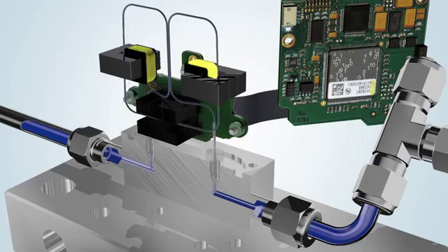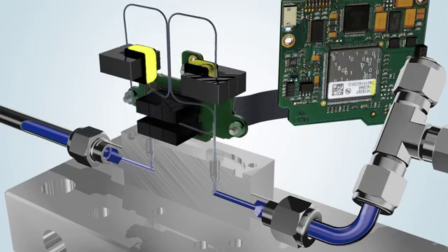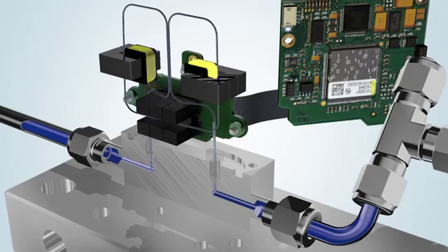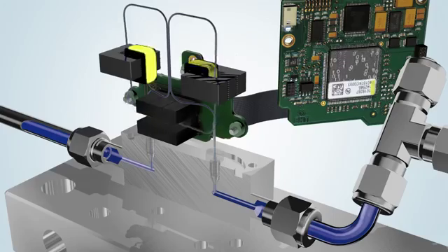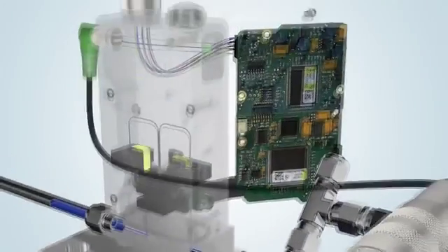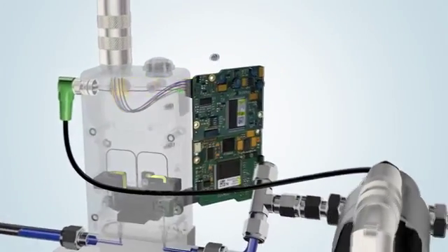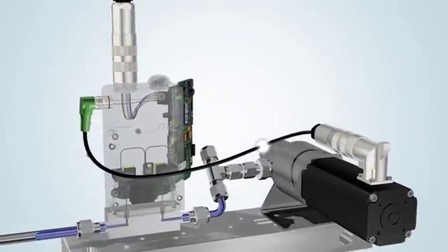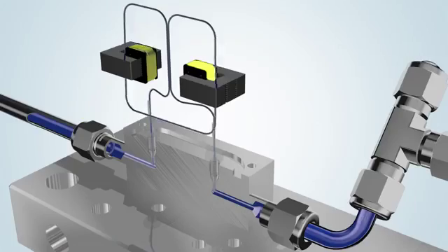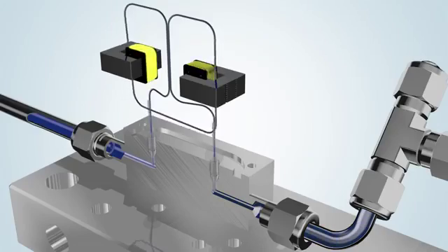The electronics compare this to the set point from a PC, PLC, or analog port. If the measured value differs from the set point value, the integrated PID controller adjusts the speed of the pump to generate the correct output. This adjustment occurs in a fraction of a second.